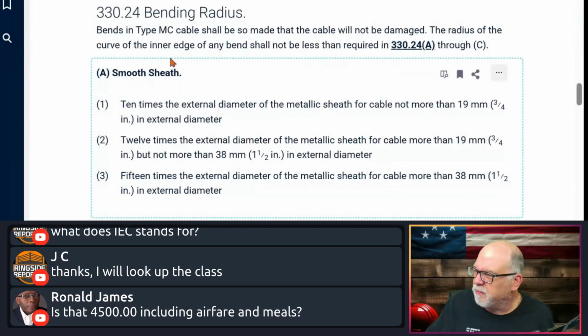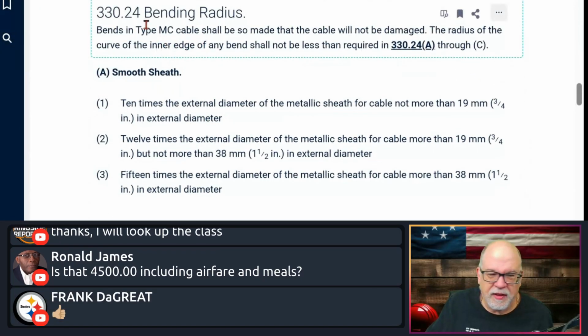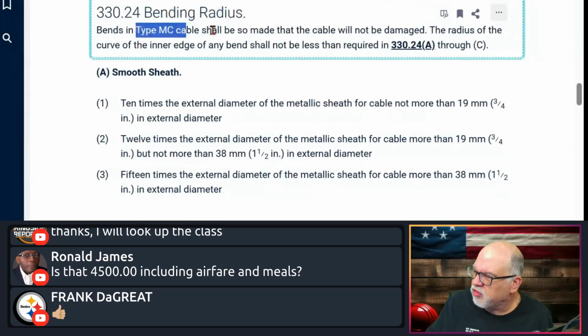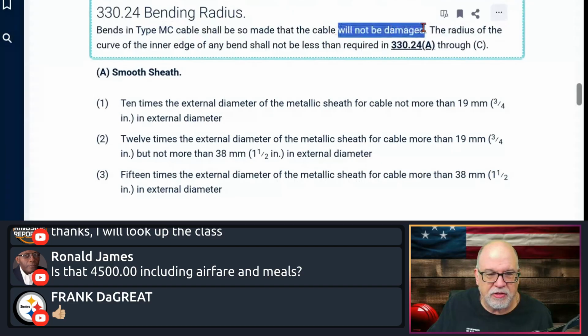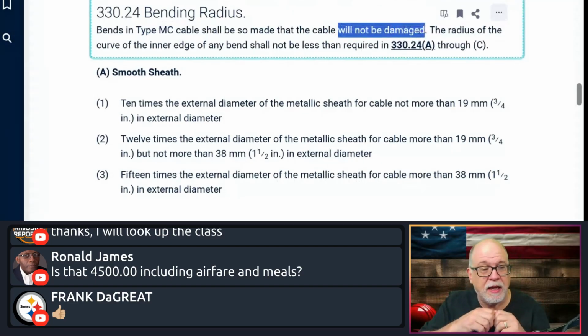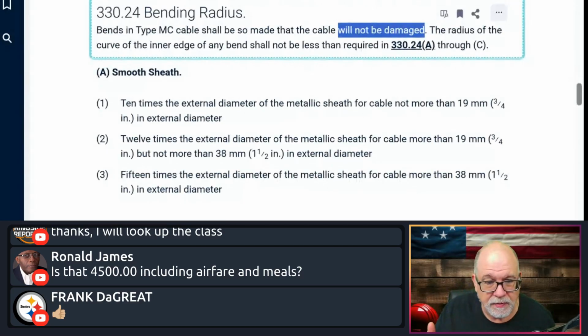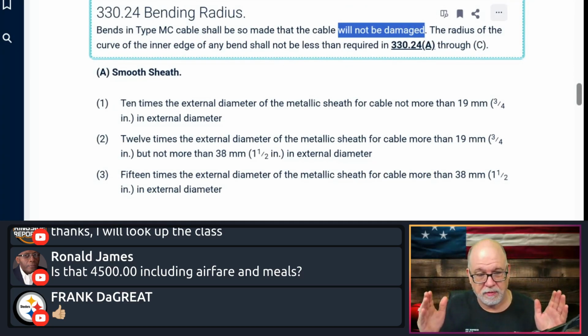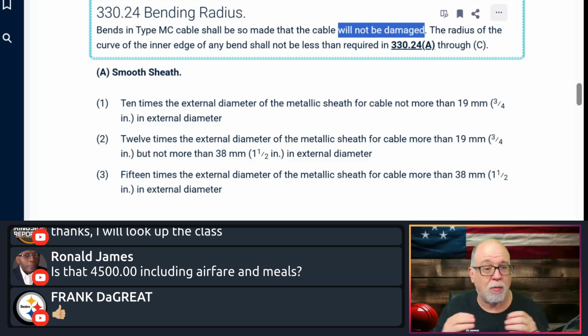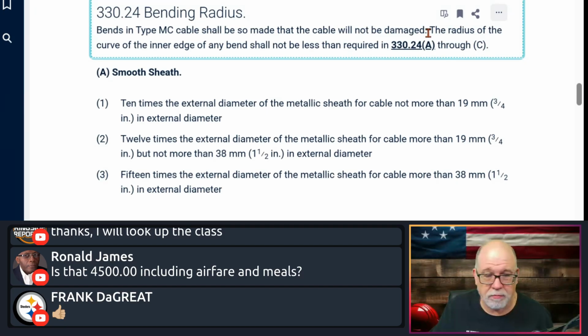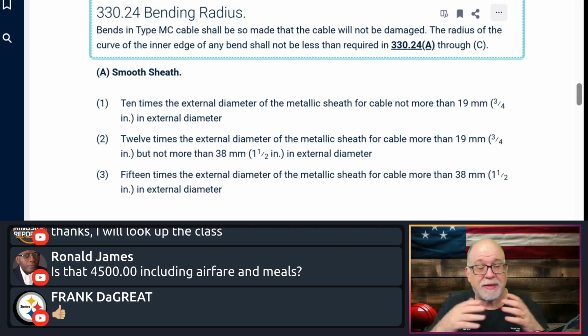All right. So bending radius. Bends in type MC cable shall be made so that the cable will not be damaged. If you bend it too tight and you pop those convolutions loose, you've damaged it. How you repair it is up to you. I'm not even going to give advice on how to repair it. I came up with a repair product that I wanted to patent, but nobody was interested in it. So I'm not interested in being a manufacturer of products. It is what it is. Now, you might be able to just tape it, but that's on you.